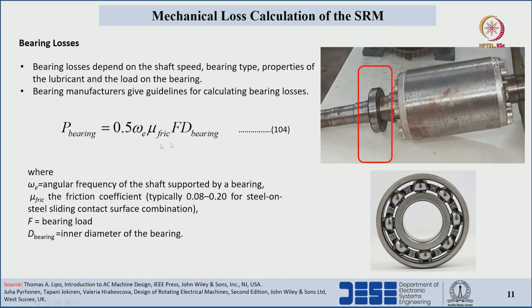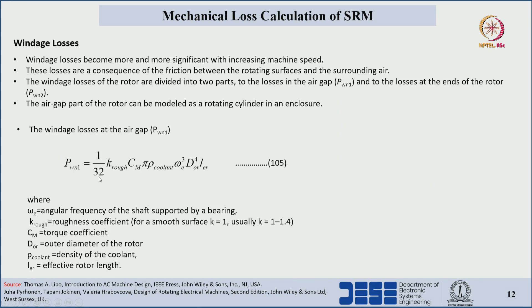The bearing loss equation is the same for both induction machines and switched reluctance machines. Here ωe represents the angular frequency of the shaft, μ represents the frictional coefficient, f represents the load acting on the bearing, and d is the inner diameter of the bearing. Windage losses are calculated based on a corresponding equation, which has already been discussed in detail.